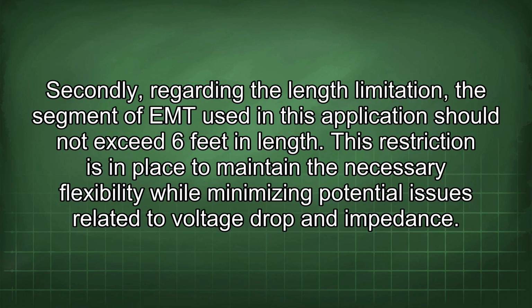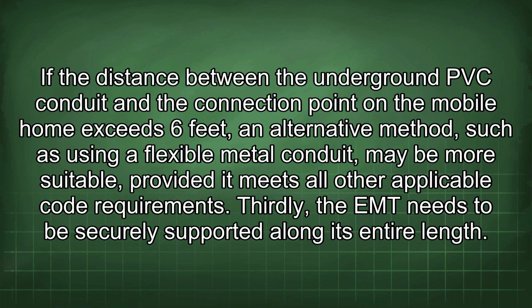Secondly, regarding the length limitation, the segment of EMT used in this application should not exceed 6 feet in length. This restriction is in place to maintain the necessary flexibility while minimizing potential issues related to voltage drop and impedance. If the distance between the underground PVC conduit and the connection point in the mobile home exceeds 6 feet, an alternative method, such as using a flexible metal conduit, may be more suitable, provided it meets all other applicable code requirements. Thirdly, the EMT needs to be securely supported along its entire length.